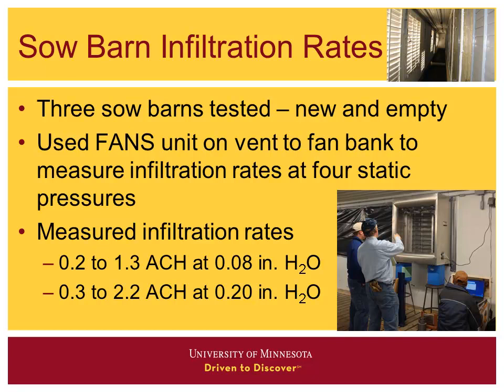He measured infiltration rates from 0.2 to 1.3 air changes per hour at 0.08 inches of static pressure, up to 0.3 to 2.2 air changes per hour at 0.2 inches of static pressure. Now, if you have an infiltration rate and a ventilation rate of one air change per hour, that's about the minimum ventilation — a major portion of the ventilation rate. So we are getting into the range where the barn's leaking enough that we're having an impact.